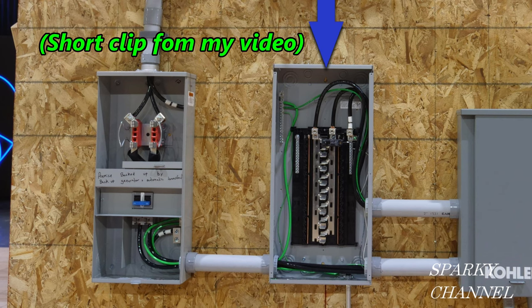This is a Siemens 200 amp 30 space main lug indoor load center with copper bus. Main lug only load centers are typically applied downstream of a main circuit breaker panel, and they can be used as a sub panel. For main lug only load centers, the incoming cables are terminated on the line side of the lugs that are attached directly to the bus. No main overcurrent device exists within a main lug only load center. From now on, I'll call this panel the MLO, which stands for main lug only.